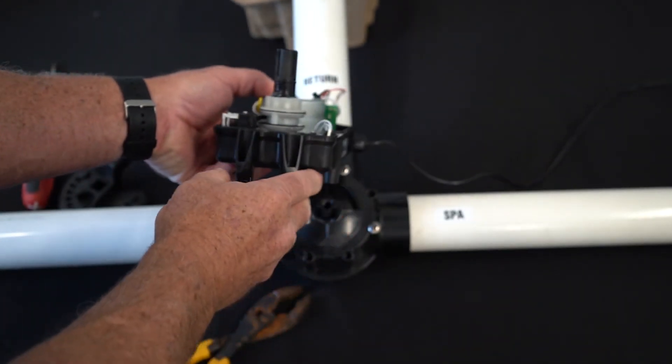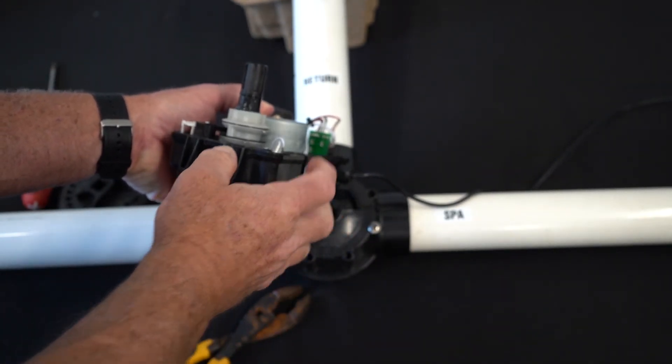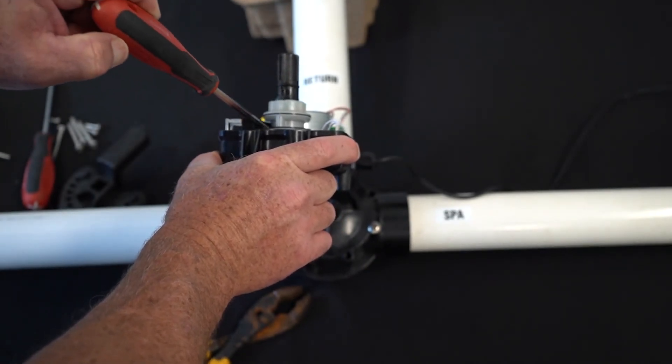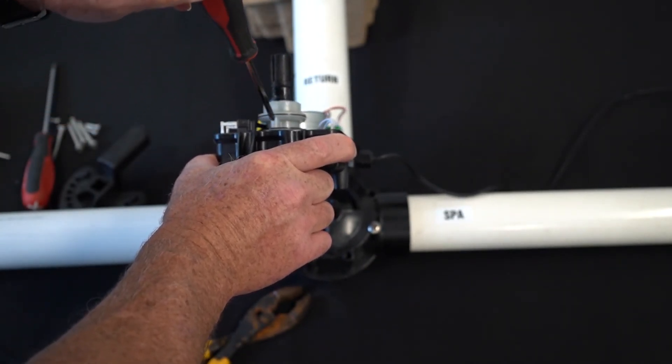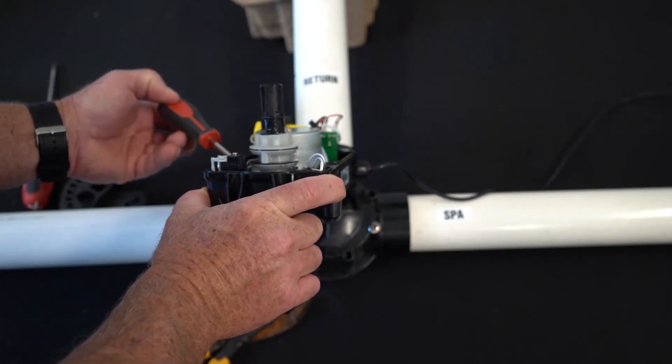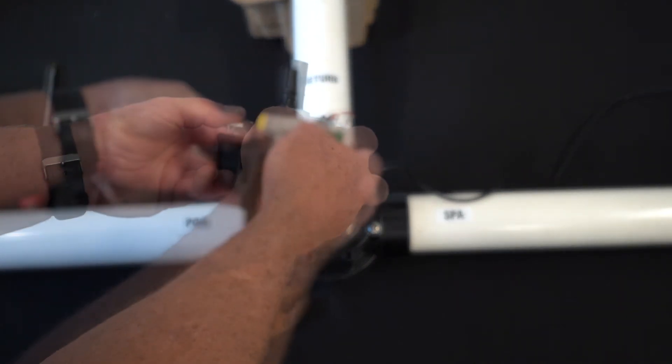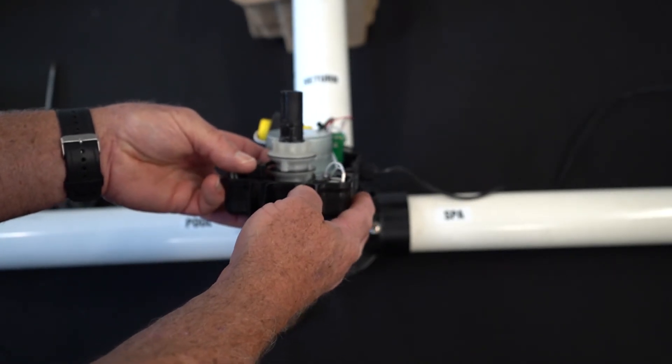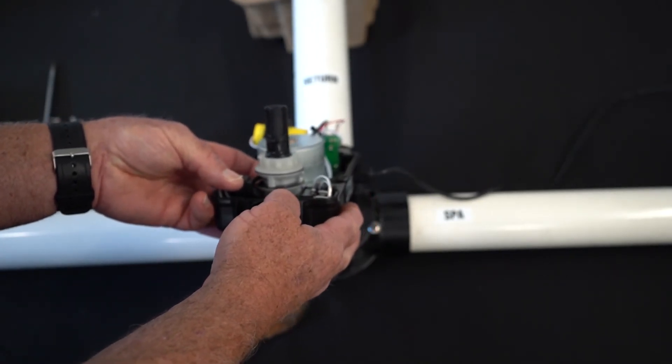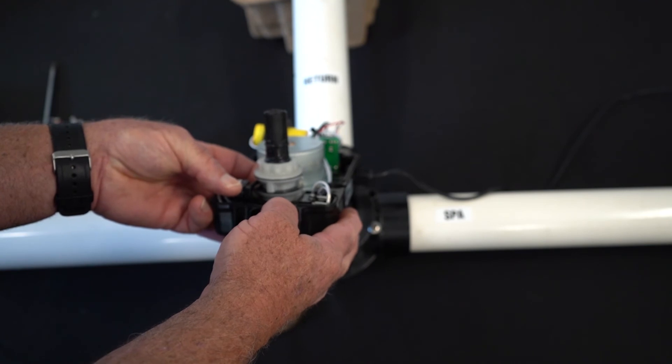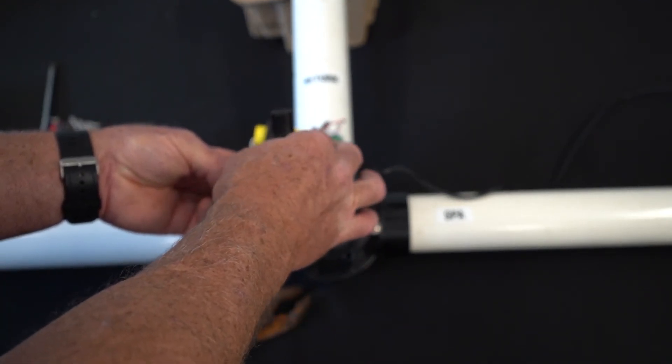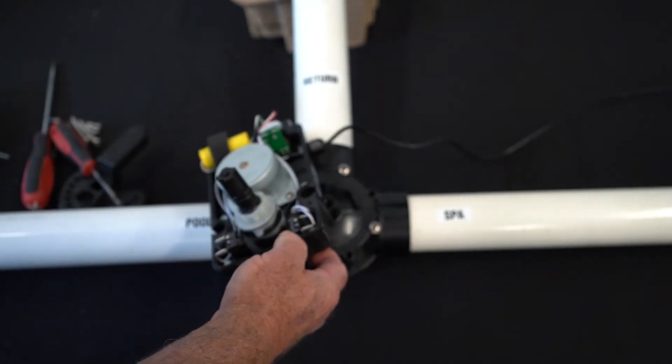And you don't want to over loosen it. And then you are going to take this lower cam and you are going to rotate it without rotating the upper one. You want to get it so that it just closes that micro switch over there. Once you get that, you want to tighten it up.